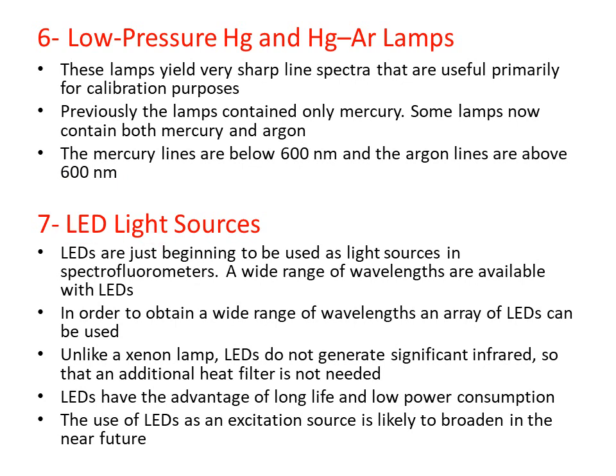The next light source is LED light sources. LEDs are just beginning to be used as light sources in spectrofluorometers. A wide range of wavelengths is available with LEDs, and an array of LEDs can be used to achieve this. Unlike xenon lamps, LEDs do not generate significant infrared radiation, so there is no need to use a heat filter. LEDs have the advantages of long life and low power consumption, and their use as excitation sources is likely to broaden in the near future.